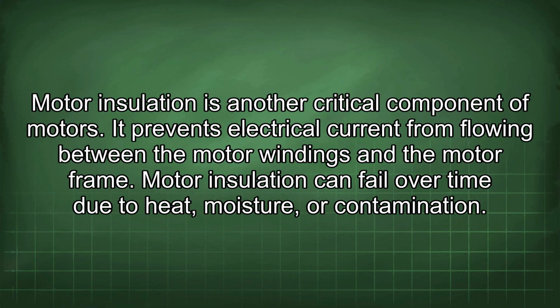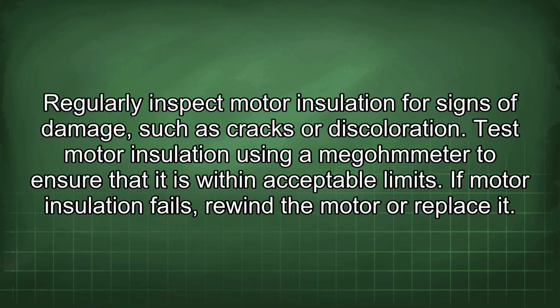Motor insulation is another critical component of motors. It prevents electrical current from flowing between the motor windings and the motor frame. Motor insulation can fail over time due to heat, moisture, or contamination. Regularly inspect motor insulation for signs of damage, such as cracks or discoloration. Test motor insulation using a megohmmeter to ensure that it is within acceptable limits. If motor insulation fails, rewind the motor or replace it.